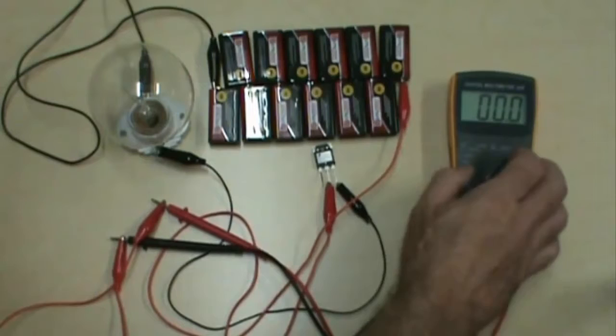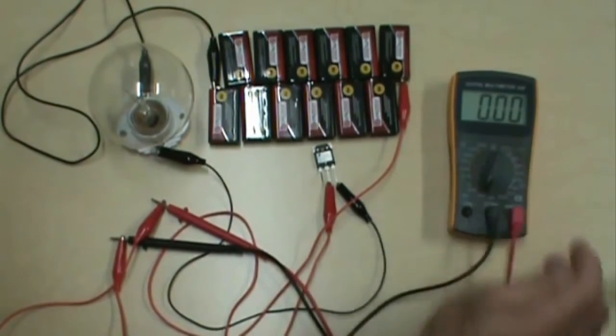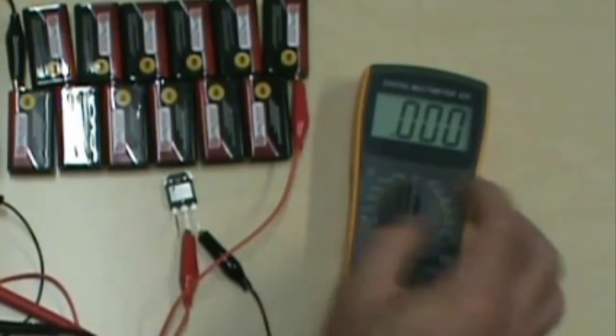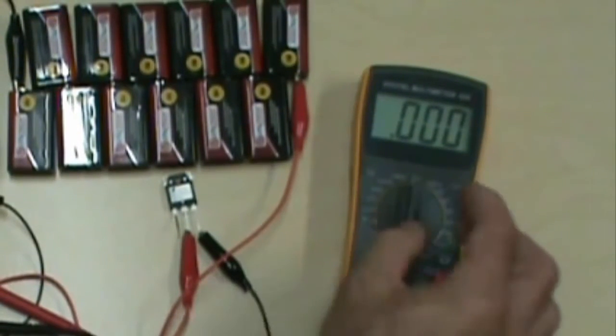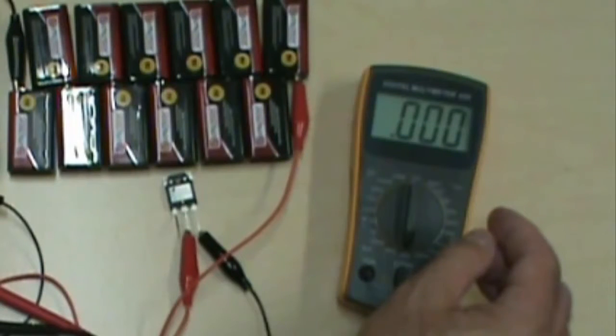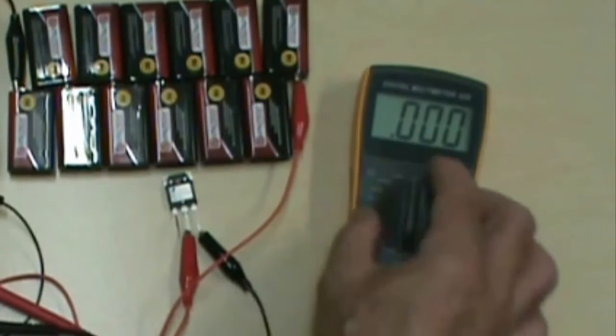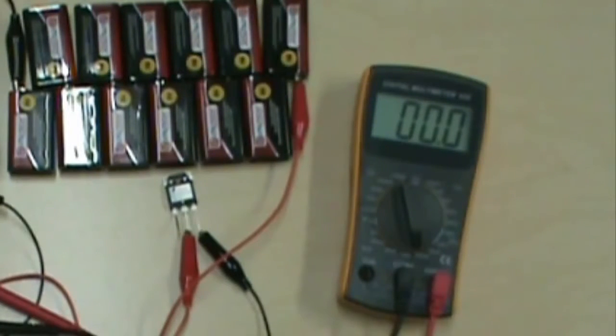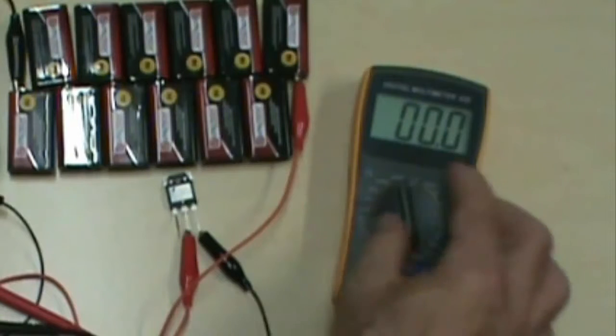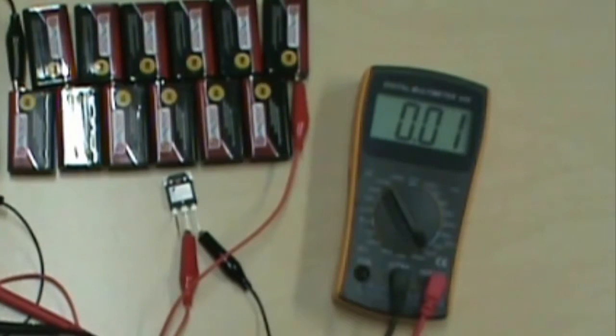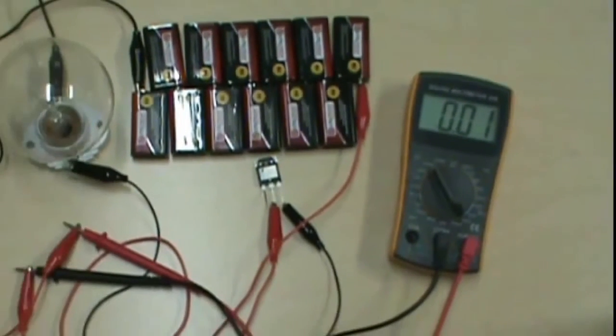So right now, no leakage at 200 milliamps full scale, no leakage at 20 milliamps full scale. It looks like it's flickering about 0.001 milliamps on the 2 milliamp scale. Put it on the microamp scale, nothing. That's the 200 microamp scale, I'm sorry. On the 20 microamp scale, it looks like we probably get about 0.01 microamps. So virtually nothing on the leakage here. And that's at 100 volts, so that's a pretty good indication that this IGBT is functioning normally, not leaking.